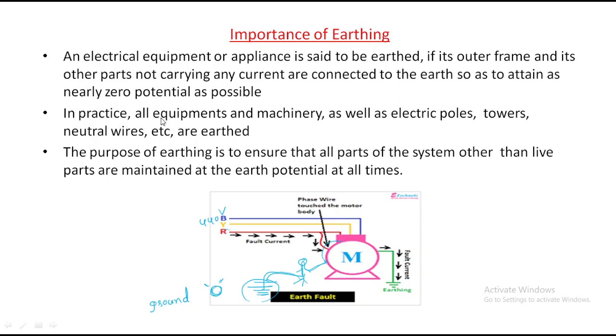In practice, all equipment and machinery, as well as electric poles, towers, neutral wires, etc., are all earthed. If you observe clearly, earthing is on each and everything. This is the machine, and electric poles also have some earthing. In the olden days electric poles were made of iron, and when we touched them we sometimes got a shock. That's why they are also earthed. Towers and neutral wires are also earthed.